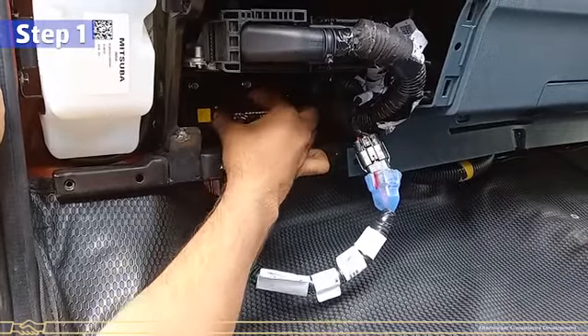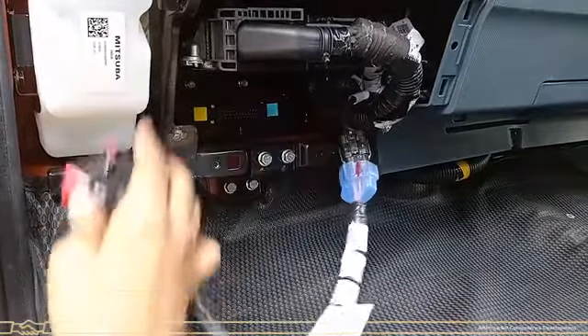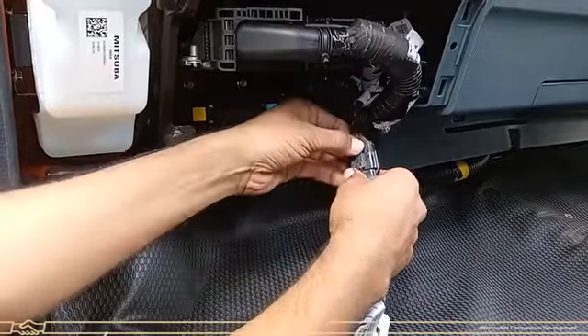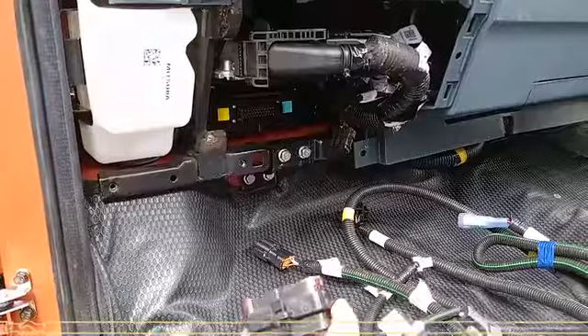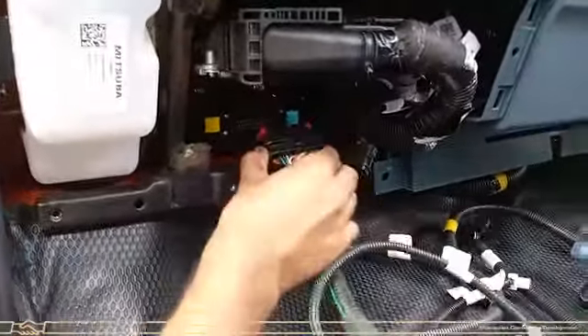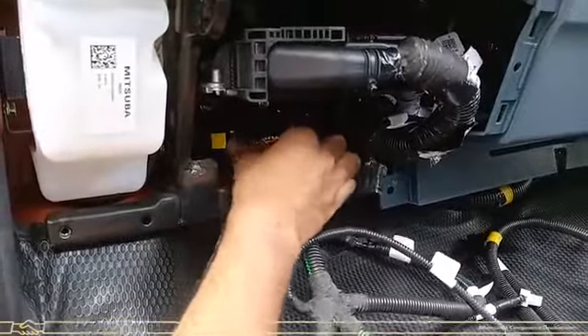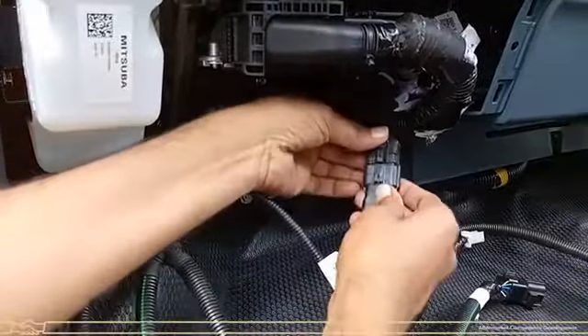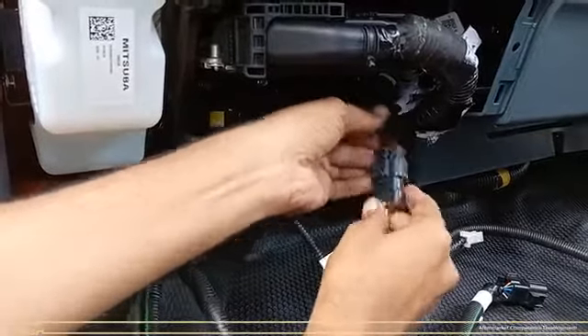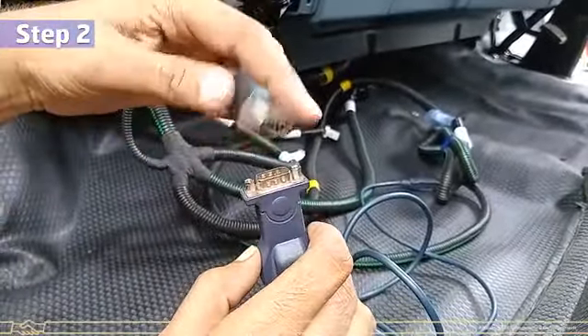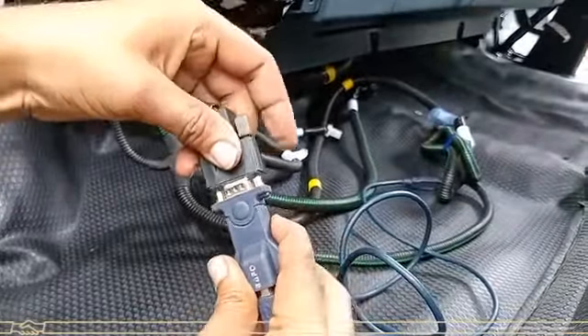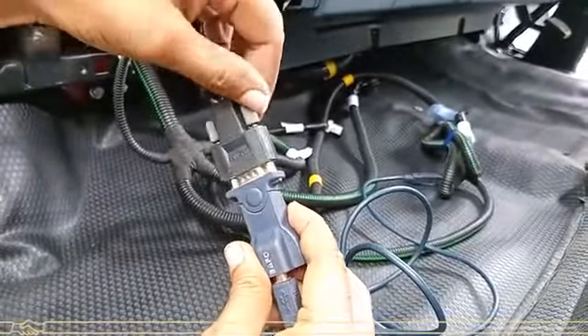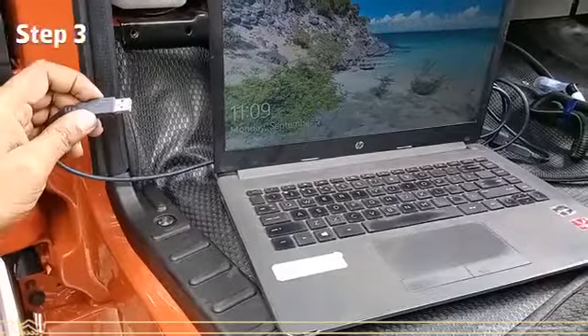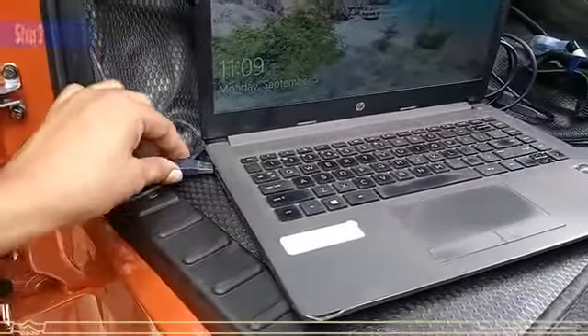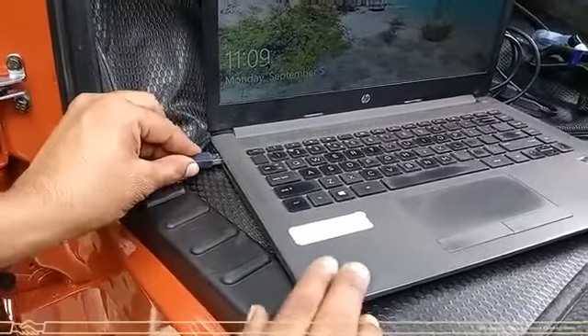Connection procedure. Step 1. Remove 35-pin connector from telematic device and 5-pin connector from harness. Connect the 35-pin cable connector with telematics device. Step 2. Connect the RS232 cable with telematics serial cable connector. Step 3. Connect the USB port of RS232 cable with laptop.